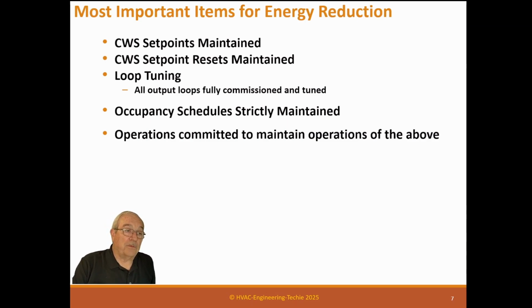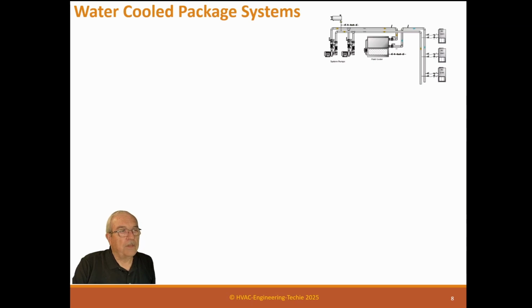So that's an operator commitment they have to make. So here's a water-cooled package system. These are standard AC units that have condenser bundles in them to condense the heat away from the units. And we use pumps to pump water around for that, and we use a fluid cooler. It's a cooling tower, but it's a fluid cooler.